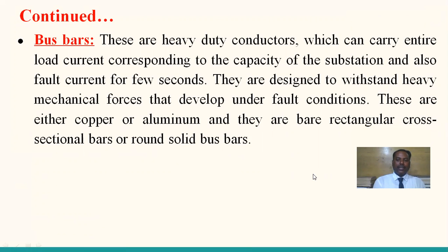So bus bar is already discussed in the layout of the substation. Bus bar is the intermediate heavy duty conductor between the incoming voltages as well as outgoing feeders. Bus bars are heavy duty conductors which can carry the entire load current corresponding to the capacity of the substation, and also fault current for a few seconds.